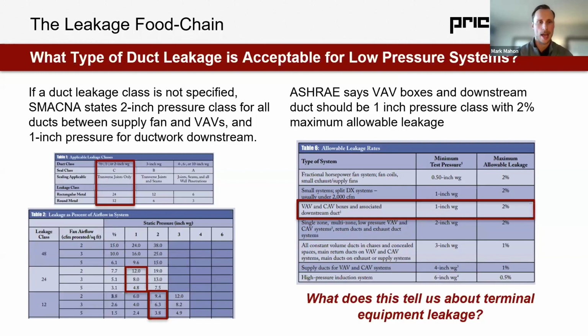At that point, we're looking at quite a few CFM potentially leaking out of the ductwork, and I would argue it's insufficient, which is why I would really stress to consulting engineers, specifying engineers, to exceed SMACNA's minimum requirements. And I think if you talk to most people at SMACNA, they would probably recommend the same thing. I think it's mostly CYA and coming up with light commercial best practices when an engineer might not even fully be involved in a project.